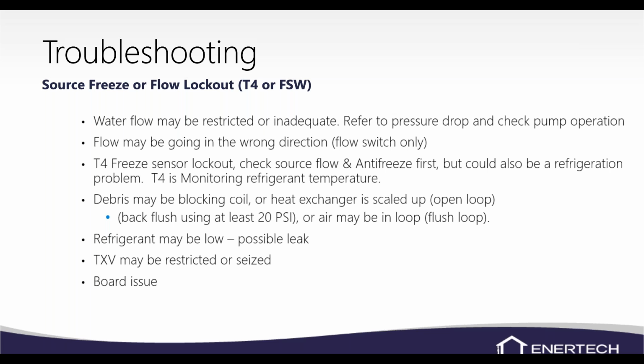Obviously, there could be a board problem or a sensor problem. If you've got a T4 sensor there, the sensor could be reading the wrong temperature, open or shorted. I will say that normally those T4 sensors don't read a wrong temperature. They'll normally just fail either open or shorted. So if it's reading resistance, it's probably good.